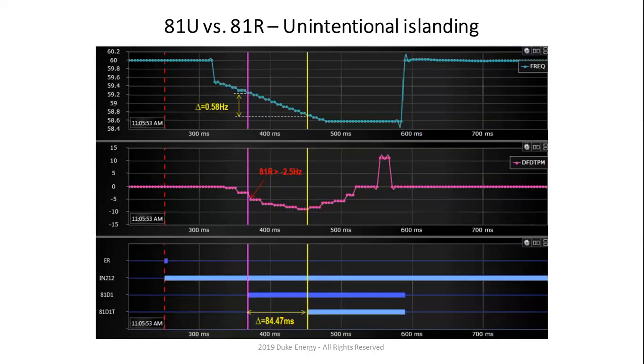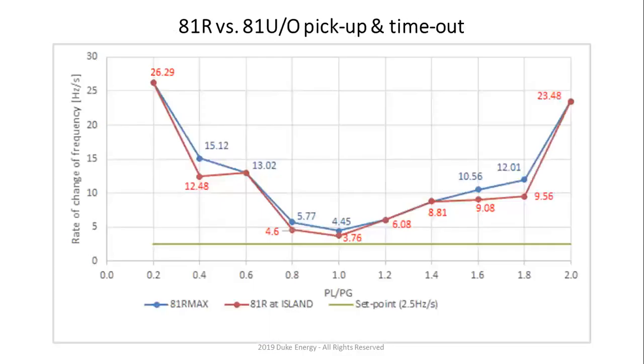So you can clearly see on this one how much faster 81R is than 81U, right? So that means probably 3 cycles faster. So we have run this again for every ratio PL over PG. I ran this with a set point of 2.5 hertz per second. Remember, as a function of PL over PG, excuse me, 81R is either going to go positive or negative. So it's essentially 2.5: if it's less than minus 2.5 or greater than 2.5, right? So just to understand how this works, we have seen that our islanding is the fastest when we have under frequency. It's much faster than the under voltage, right?